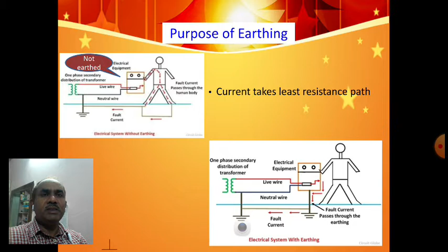Now in this case we connect the body of the electrical equipment to the ground. Then the fault current goes directly to the ground instead of going to the person, because the person has his own resistance of 500 to 1000 ohms. So it will flow directly to the ground instead of through the person, and the person will not feel an electrical shock. This is the purpose of earthing.